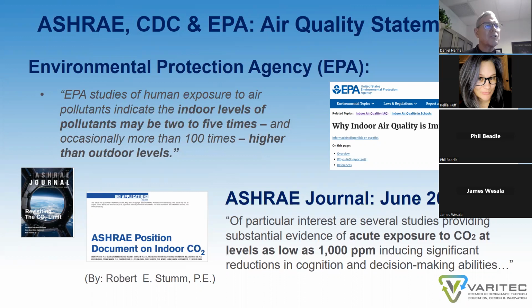So if you adopt ASHRAE 62.1, 700 parts per million delta between indoor and outdoor as a baseline for indoor concentrations, you're now seeing concentrations in the realm of 1,200 to 1,300 parts per million. And recent studies have demonstrated that cognitive faculties can be impacted by CO2 concentrations of 1,000 parts per million. So there's a push now occurring in the background advocating for CO2 levels of between 600 and 800 parts per million. The only way you can do that is to increase your outside air.